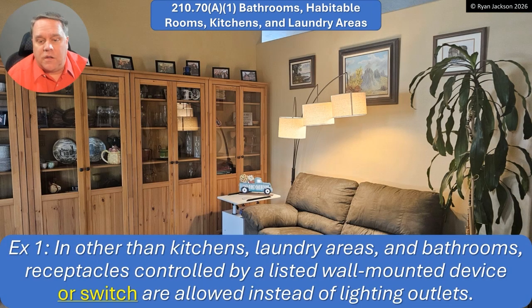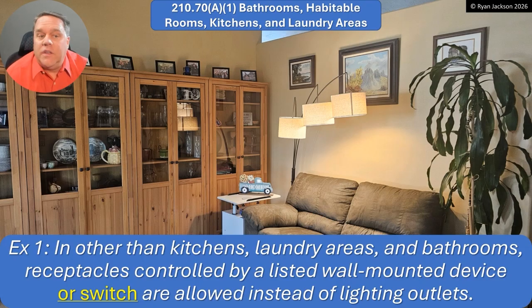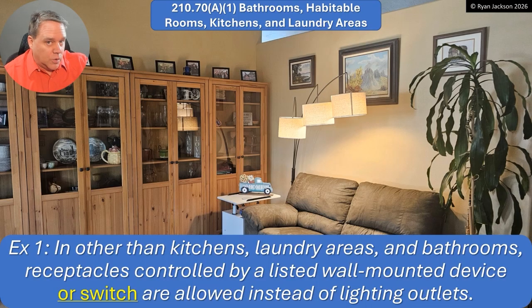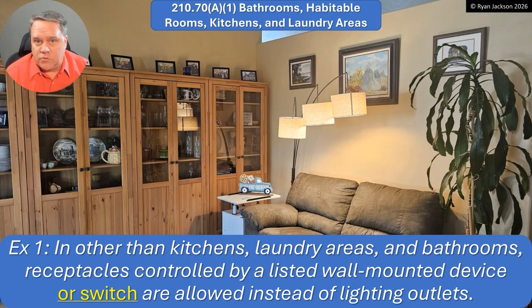In other than kitchens, laundry areas, and bathrooms, receptacles that are controlled by a listed wall-mounted device or switch are allowed instead of lighting outlets. So you can still use switched receptacles, but you can't use a switched receptacle in lieu of lighting in the kitchen, laundry, or bathroom. In the living room or a bedroom, be my guest — switched receptacles, plug in a lamp, you're good.